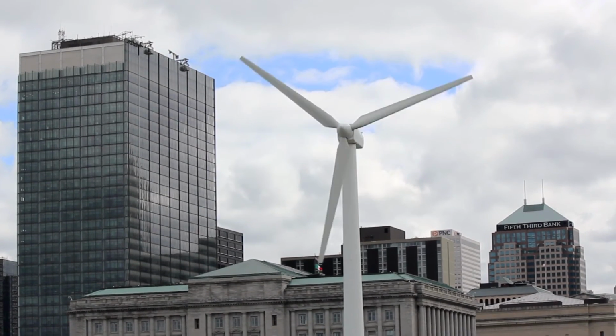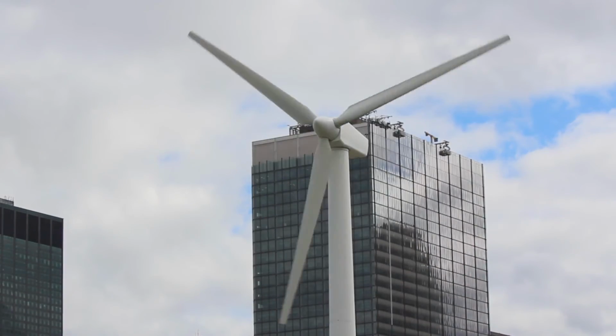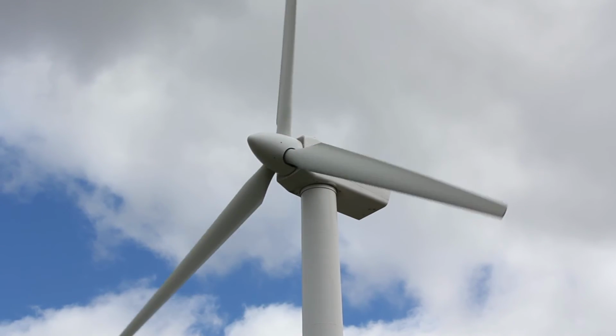And who will benefit from the power then? Will it feed right into the grid here in Cleveland, or how will that work? Well, one of the other pieces of the story that Fred also reminded me of is that we have 2.8 gigawatts of unused substations along the lakefront, old coal plants. We have a 2-unit nuke plant where only one unit was built. So we have another substation there that could be utilized. We plugged into the Cleveland Public Power Lake Road substation, which is an old abandoned 40 megawatt coal plant. That plant was shut in the 70s, but the infrastructure and the substation are there, so we were able to plug right in. The future vision is that wherever we go in the lakes, we will already have an existing substation to plug into.